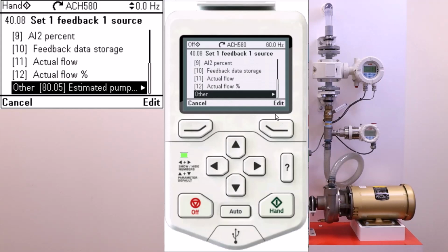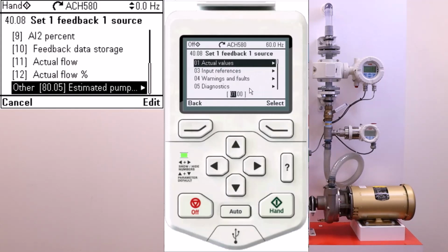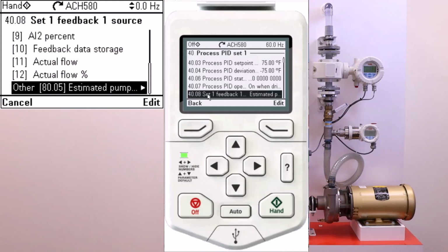We go to other, we go edit, and now we go to group 80. And there's 80. That's our flow calculations. So we select group 80. And 8005 is our estimated pump head. So this is our calculated pump head. And this is what we want to aim for in our PID loop right now. So we'll save that. So right now our new feedback source is estimated pump head.